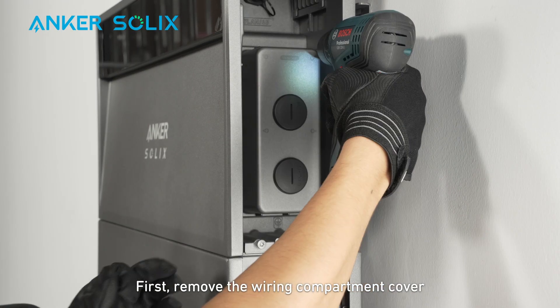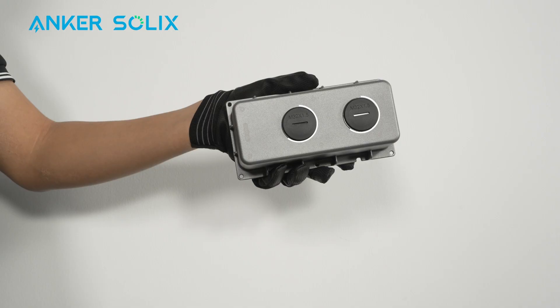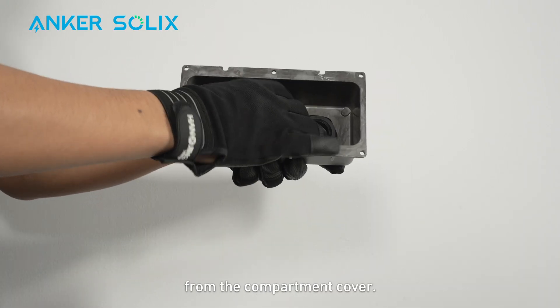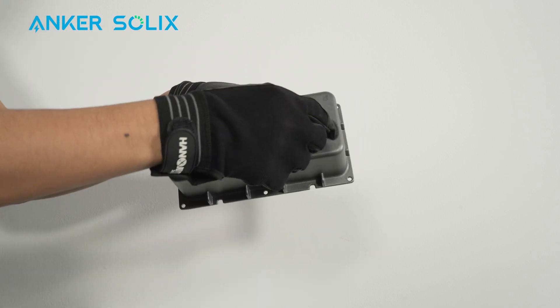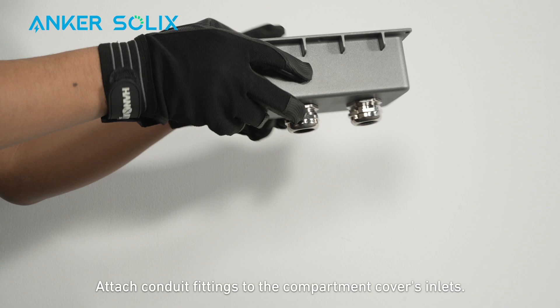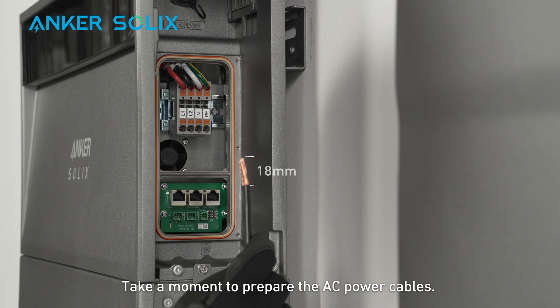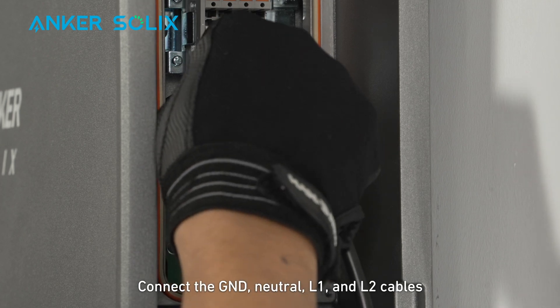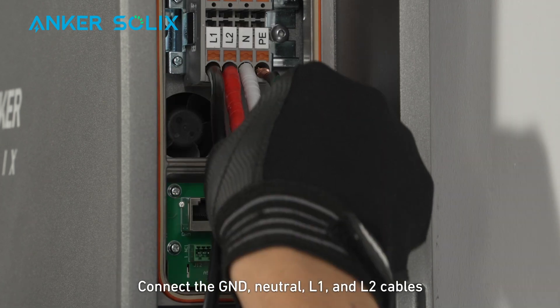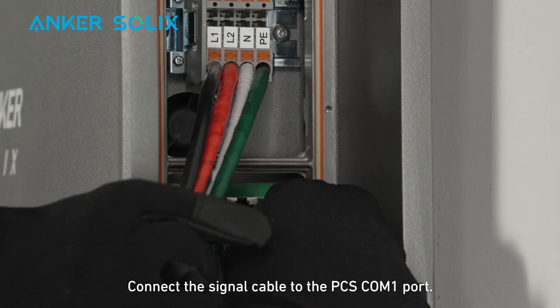First, remove the wiring compartment cover from the right side of the power module. Rotate the inner rings to remove the stoppers from the compartment cover. Attach conduit fittings to the compartment cover's inlets. Take a moment to prepare the AC power cables by stripping 18 millimeters of insulation. Connect the ground, neutral, L1, and L2 cables to the power module. Connect the signal cable to the PCS COM1 port.